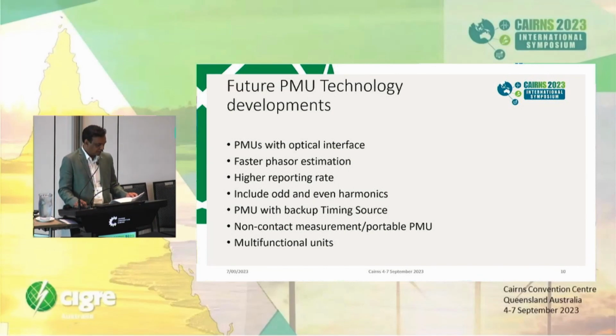Connecting PMUs in existing circuits can be challenging sometimes, and portable or non-contact PMUs can also be a good solution to check healthiness and accuracy of the circuit. Multifunction devices that combine phasor and power quality values such as harmonics, voltage sag, swell, signal to noise ratio, and voltage flickers provide better value. PMUs can also provide point-on-wave data. Hence, PMUs integrated in comprehensive power system monitoring units will provide a better value proposition. Let's look at some of the integration requirements.